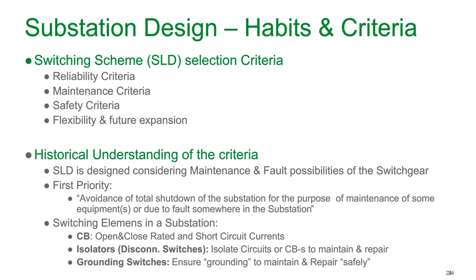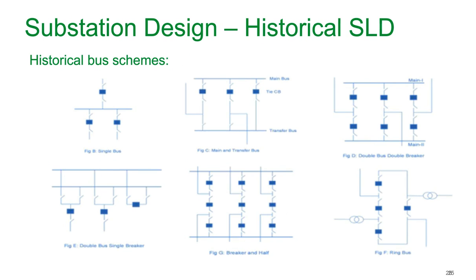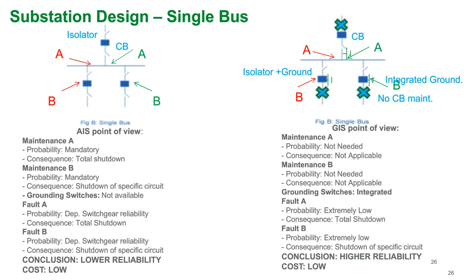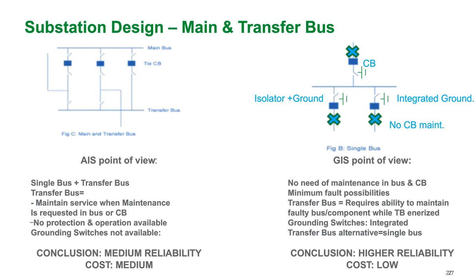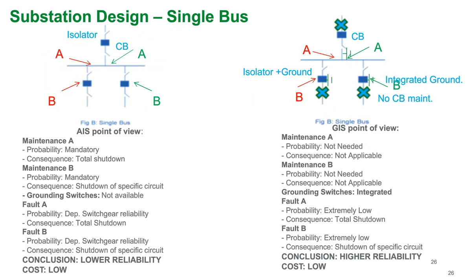So there are some different approaches to different types of protection. I'm going to focus on these 6 concepts. We're going to go all the way from a standard single bus arrangement, which is everything from just a main with feeders to main-tie-main with feeders or the like, all the way down to ring bus configurations. Skip through a slide real quick, sorry, everybody. On the left here, single bus, from the air-insulated point of view, we're going through maintenance and then faults.